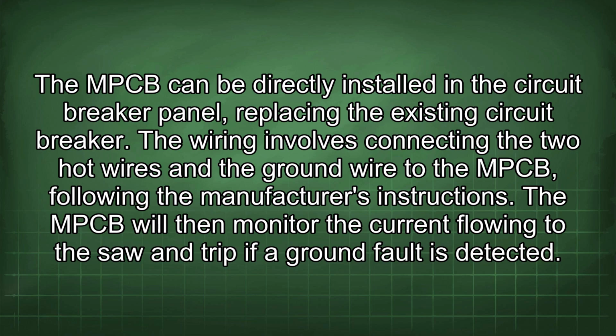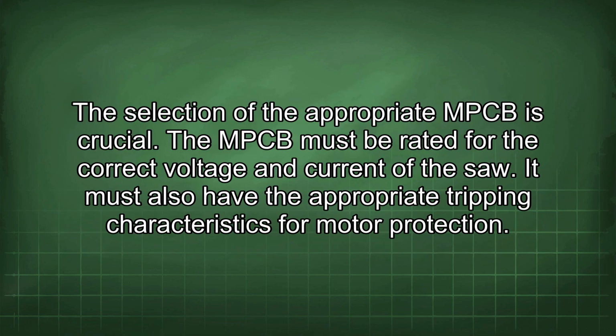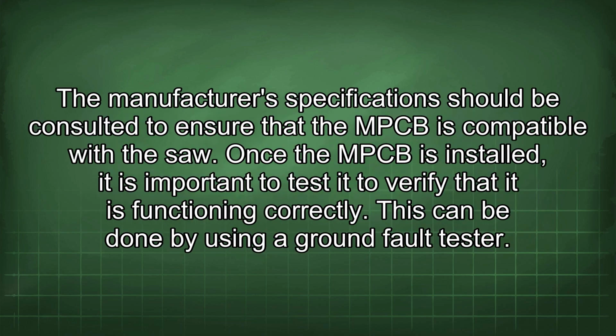The wiring involves connecting the two hot wires and the ground wire to the MPCB following the manufacturer's instructions. The MPCB will then monitor the current flowing to the saw and trip if a ground fault is detected. The selection of the appropriate MPCB is crucial. The MPCB must be rated for the correct voltage and current of the saw. It must also have the appropriate tripping characteristics for motor protection. The manufacturer's specifications should be consulted to ensure that the MPCB is compatible with the saw.